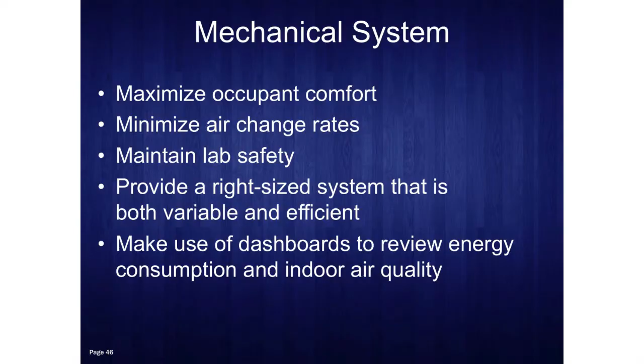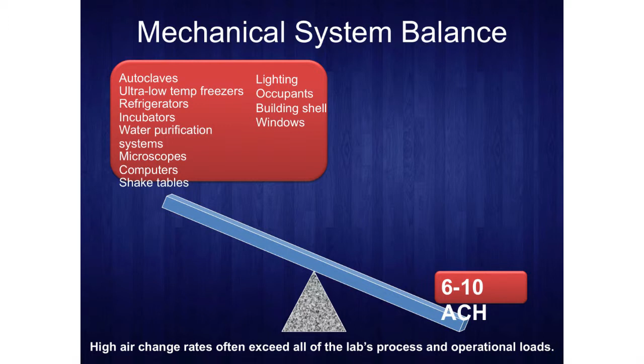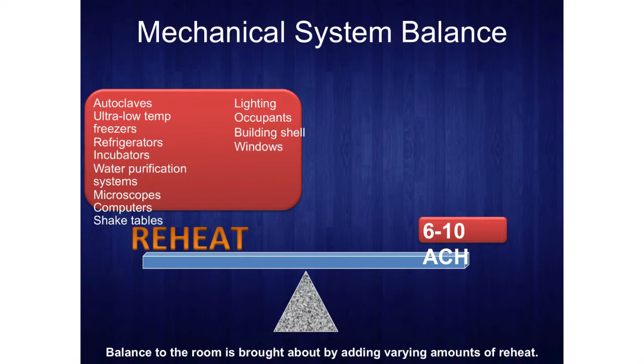So let's take a look at it from a really simplistic atmosphere. Mechanical system balance, right? Right now, you have all of this equipment in your laboratory space, and you have maybe these kinds of air changes. And if you're supplying 55 to 60 degree supply air temperature, you have to add reheat to bring it into balance. And then you can balance out at your high air changes, not a problem. If we take that reheat away, the system falls out of balance, right? You want to drop those air change rates, and you still have that reheat.